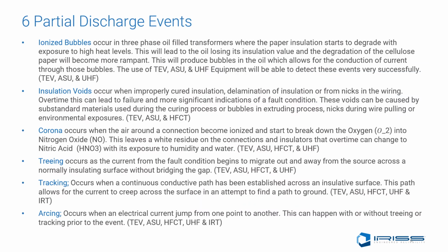There are 6 types of partial discharge that can be detected using TEV or ASU devices. Infrared will pick up 2 of these, which in turn helps to prove the exact fault condition occurring inside the asset by process of elimination and correlation. We discussed already the ionized bubbles occurring in oil-filled transformers. We also covered insulation voids and what they can do. We discussed corona. Now let's discuss treeing.